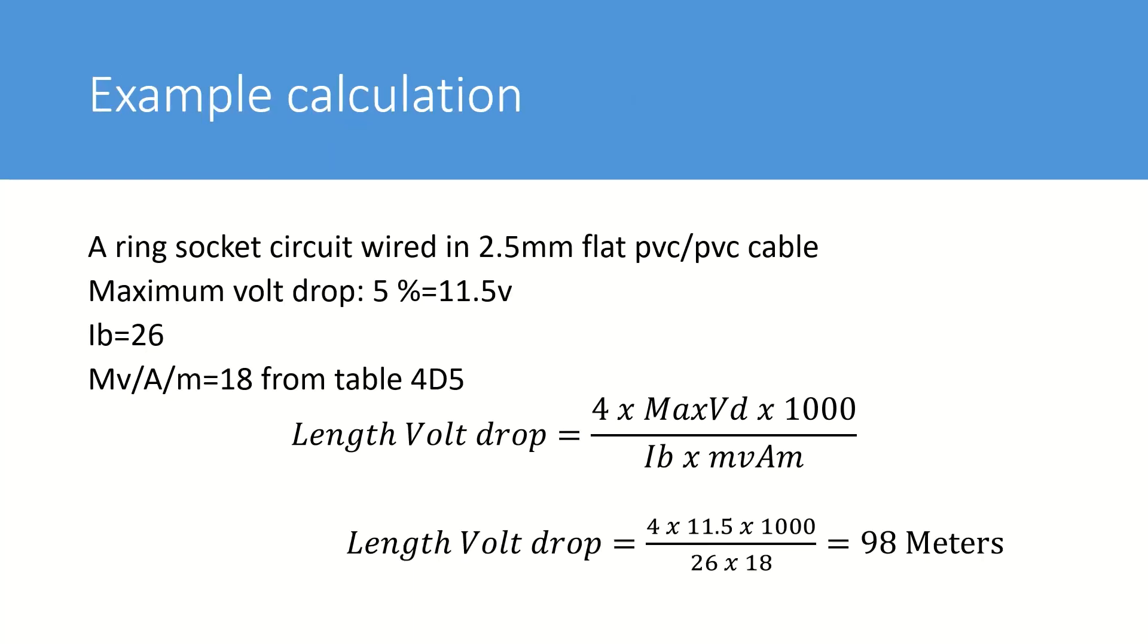So here we have an example calculation. If we take the example of a ring socket circuit wired in 2.5mm flat PVC cable with a maximum volt drop of five percent which comes to 11.5 volts. The design current we've taken to be 26 amps and the millivolts per ampere per meter is 18 and that's taken from table 4D5.